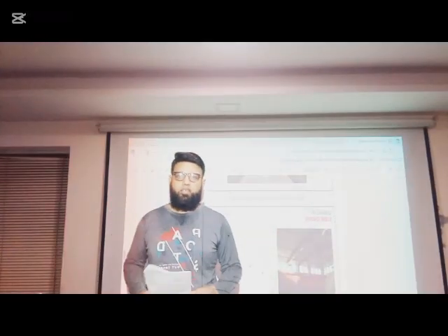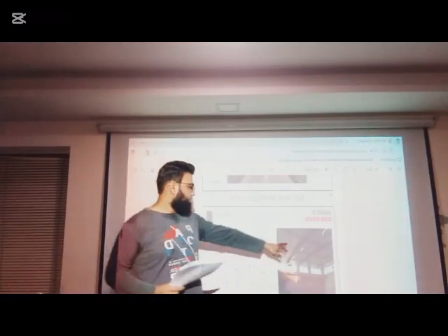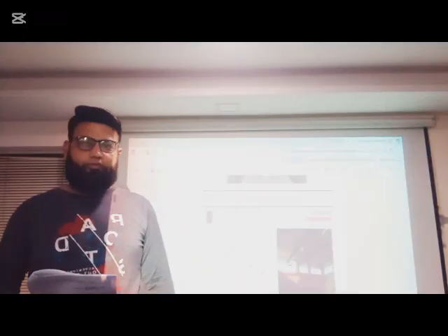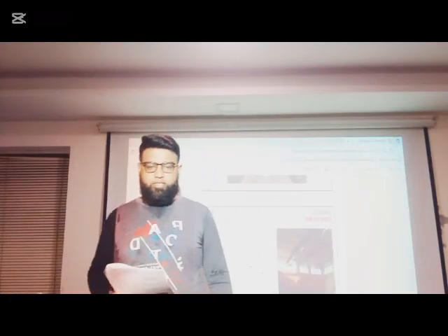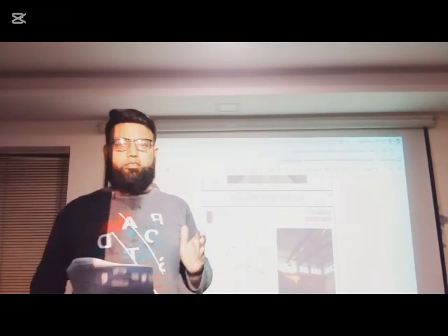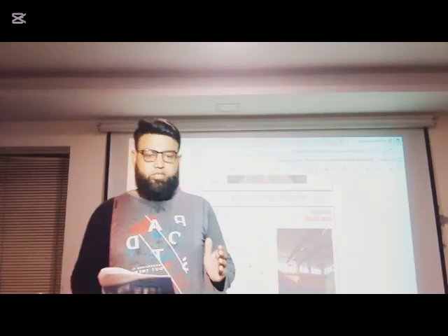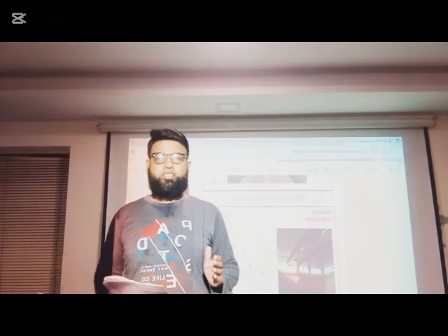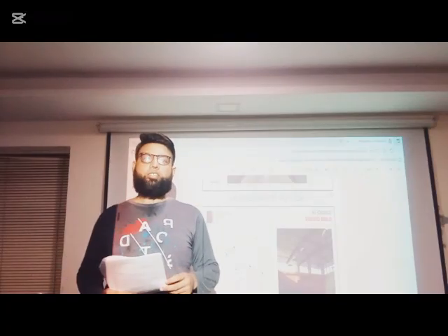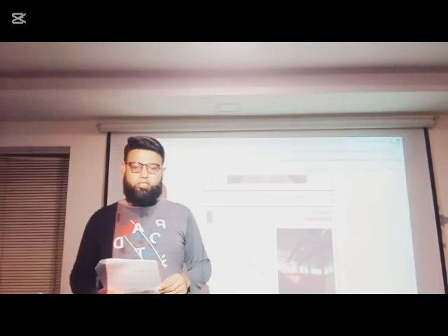So the next is the cloud ceiling. What are cloud ceilings? As you can see in the picture, the distance between the ceiling is called the cloud ceiling. So what are the requirements which need to be fulfilled so that the cloud ceilings may not be sprinkled? The opening between the cloud ceiling should not exceed 20% of the ceiling area. The second is that the above ceiling construction is non-combustible or limited combustible. Moreover, the ceiling height should not be more than 20 feet. Only then the cloud ceilings may not be sprinkled.